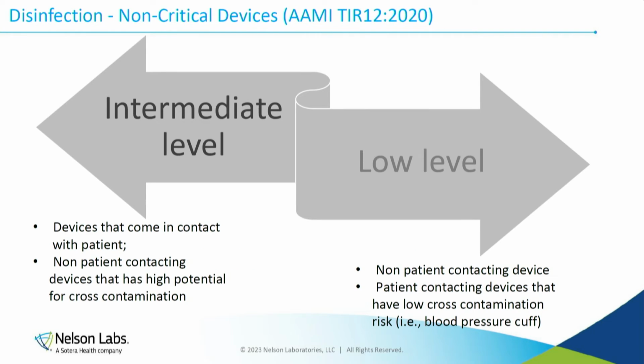Now with the intermediate and low level TIR12, it's a gray zone. It's non-critical, but where do you put it? It depends on how close your device is in contact with the patient, or how we should evaluate cross-contamination. That's what manufacturers are. There is no list that says if you're here, you do this. If you're here, you do this. These two are both in the non-critical zone. You will have to evaluate if it's intermediate level disinfection or low level disinfection. And that is determined upon the proximity of that device to the body and if it's cross-contamination.